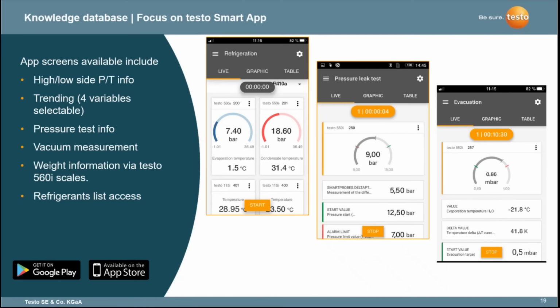You can trend up to 4 variables, so you can actually have a trending view, a bit like data logging, so it's much more graphic. You've got the pressure leak test, the evacuation mode. You've got the ability to link, say, to the 560 scales and the automatic charging. And also all your refrigerant lists can also be accessed through the app as well.